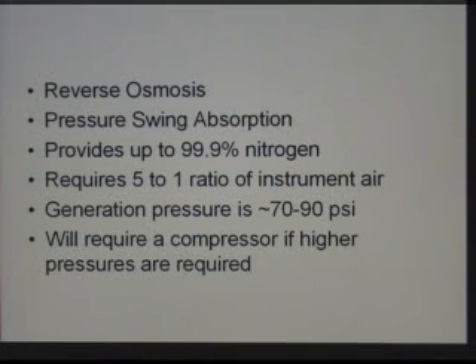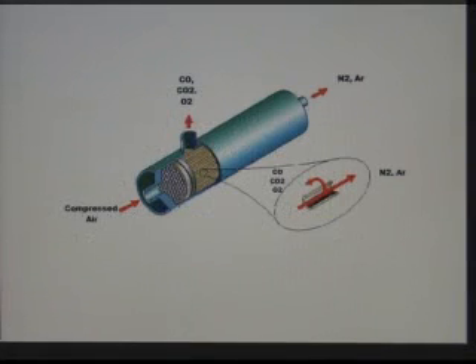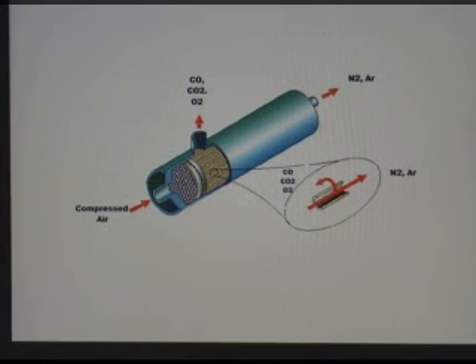Because it uses instrument air and there is a pressure drop, your pressure is only going to be between 70 to 90 psi. So if you need higher nitrogen pressure, you need a compressor to take it up to whatever pressure level you're after. So this is the reverse osmosis style. Compressed air comes in, oxygen, CO2, carbon monoxide, anything else comes out, including water. And then out the ends of the tube is just nitrogen and argon. So because of that, you have very high purity nitrogen. You also have extremely dry nitrogen, very, very minimal water content inside of there.